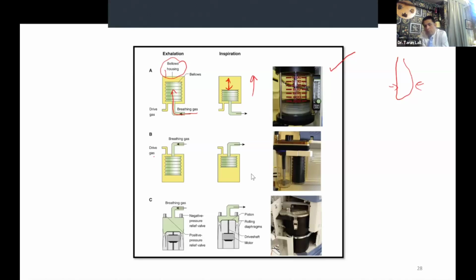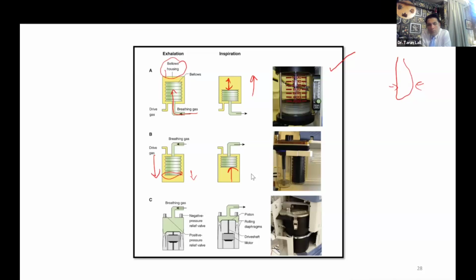The descending bellows was absolutely the opposite. In this, for the gases to fill up, there was a weight. So the bellows would fall, the gases would fill up, and then in the next breath, the bellows would move up and provide inspiration. If we compare the safety of the two devices, the descending bellows will descend even if there is a leak in the bellows, even if the entire tidal volume is not being delivered to the patient. Whereas in the ascending bellows, and this is what you have seen every day, whenever there is a leak, the bellows will just collapse, not allow any kind of ventilation to happen, and it will trigger the alarms. So this is generally considered the safer mechanism.